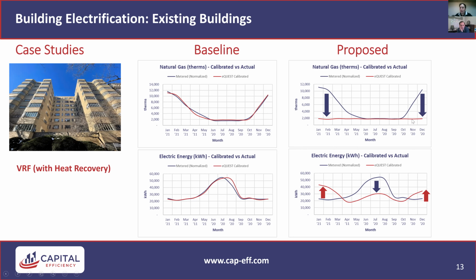In this case, domestic hot water and laundry were left out of the conversion. But on the flip side, you're going to increase electric energy during winter months where you weren't before. VRF is very efficient though, especially with heat recovery. You can simultaneously heat and cool and share that heating amongst various units, so even in summer months the cooling load is lower just by being more efficient.